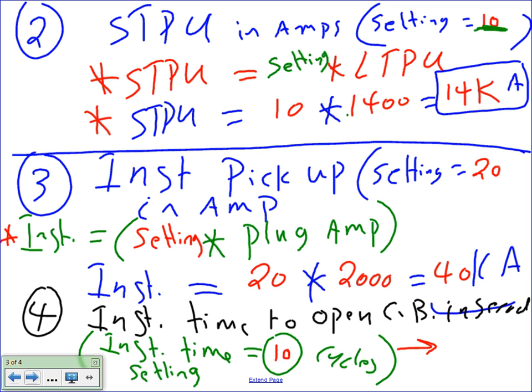Now, instantaneous time to open the circuit breaker in seconds. I set the instantaneous time. This one, the instantaneous pickup is in amps, and instantaneous to open is in time. I'm setting it at 10 cycles. Guys, they set instantaneous as cycles. So if the instantaneous is set at 10 cycles, how many seconds would it take the circuit breaker to trip?